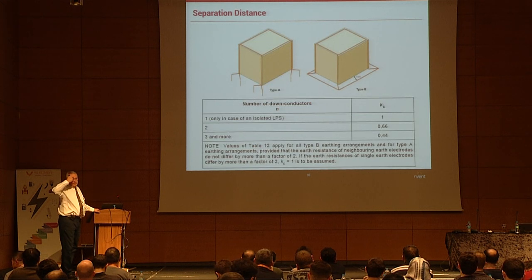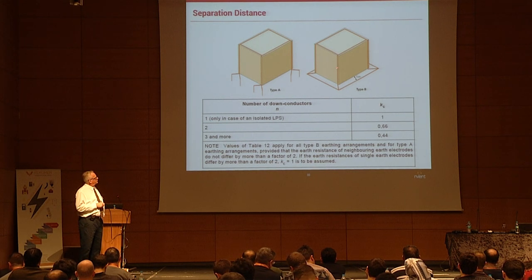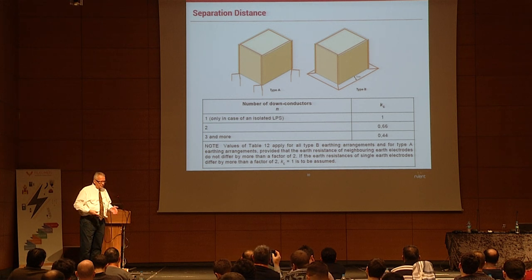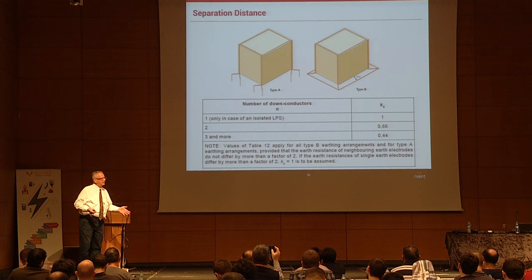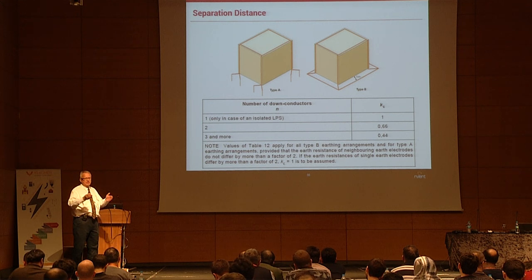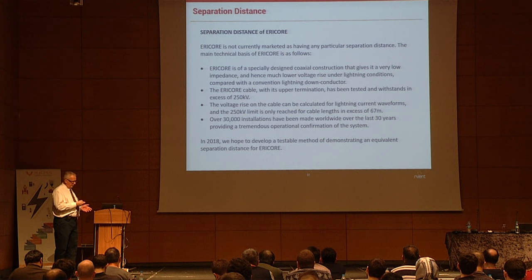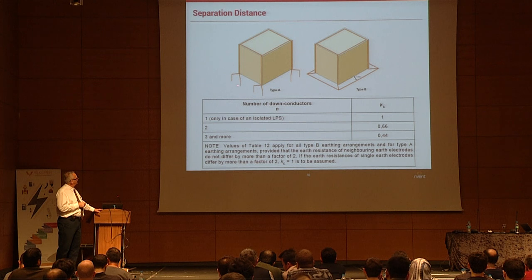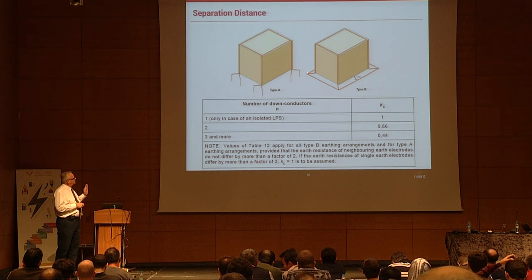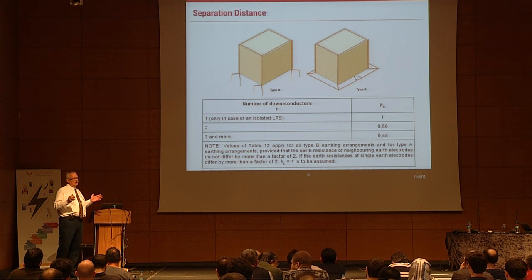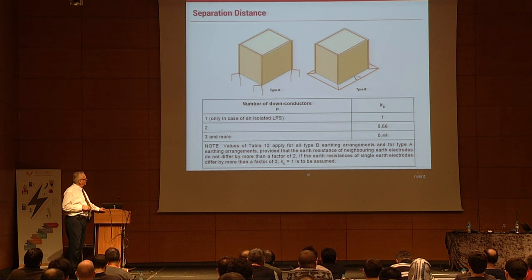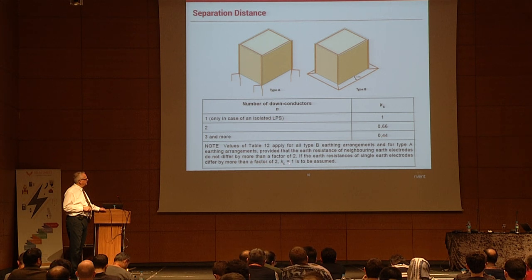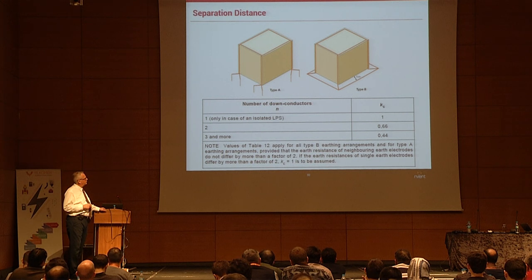Another important aspect is the grounding system. A ring ground around the building foundation creates an equipotential system with pretty much the same resistance wherever you measure. With four separate independent grounding systems — one for each down conductor — if the systems are within a factor of two from each other in resistance, you're okay. If not, you must assume Kc equals one. If there's a factor-of-two difference between individual grounding systems, you have to change Kc to one.